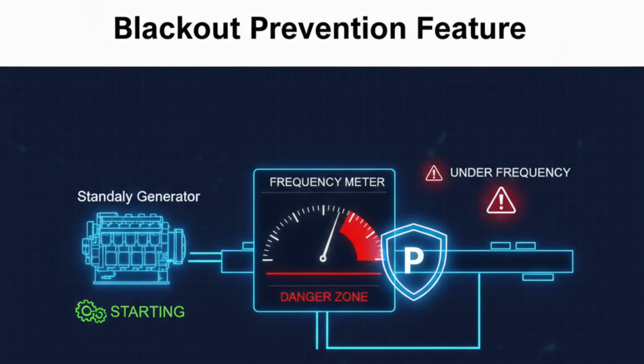Blackout prevention feature. Blackout prevention is one of the most critical functions of PMS. The system constantly monitors frequency and voltage. If frequency drops rapidly, it indicates overload or an impending generator trip. Before the system fails, PMS automatically starts standby generators and sheds non-essential loads to stabilize the network.